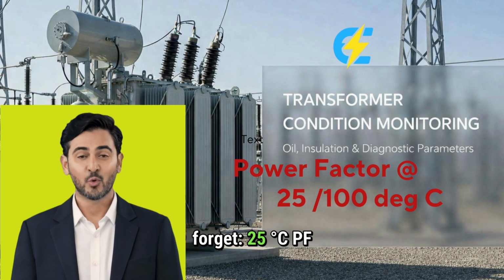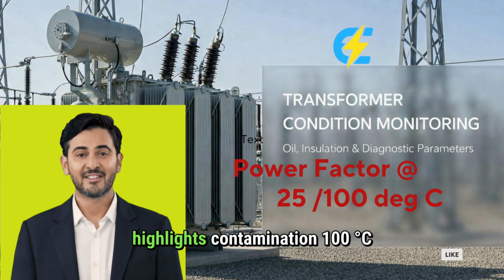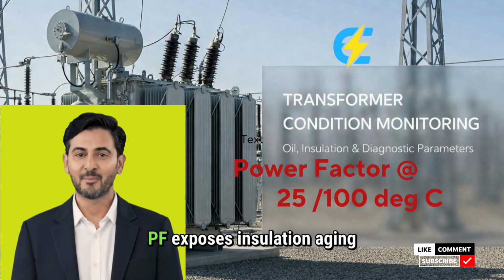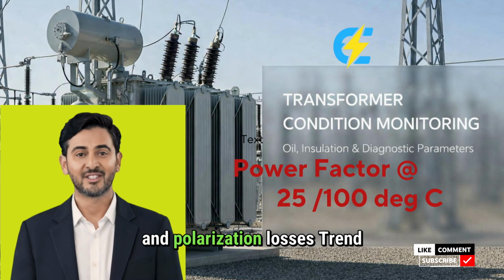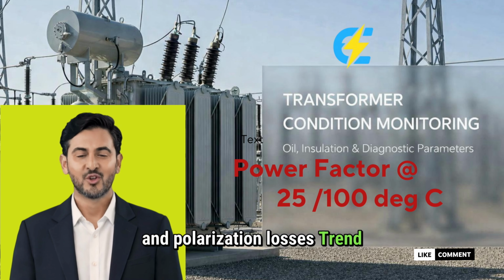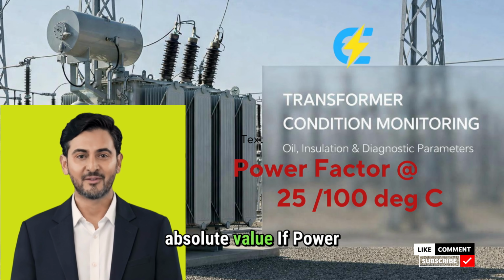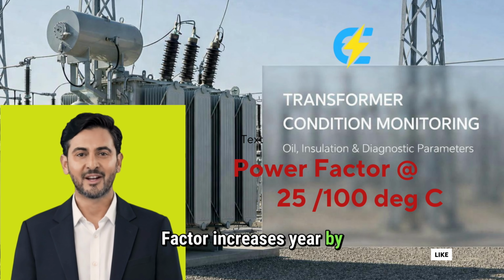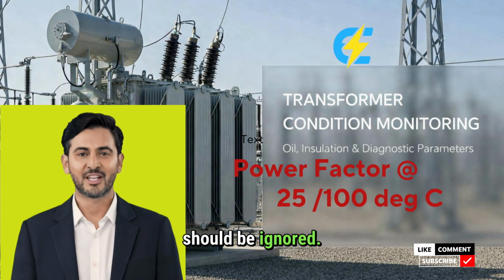And never forget, 25 degrees PF highlights contamination. 100 degrees PF exposes insulation aging and polarization losses. Trend is more important than absolute value. If power factor increases year by year, no oil test should be ignored.